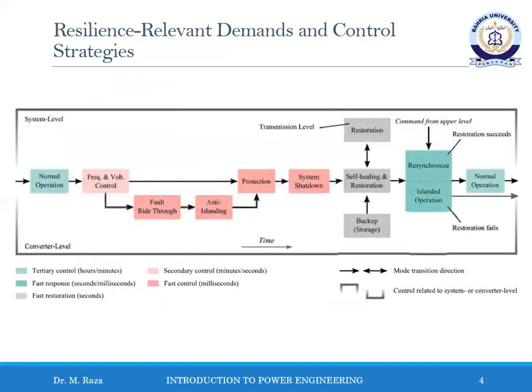In this flow diagram, the operating time sequences for the distribution power generation system are shown in connection with the resilience of the distribution grid implemented at different levels. In normal operating mode, the distribution power system should be controlled at the converter level, while it should also be coordinated among the entire distribution system. In the case of an unexpected temporary grid incident, the grid voltage level may decrease significantly. During this period, the distributed generator should remain connected for a short period, being the fault ride-through operation. They must support the fault ride-through operation.